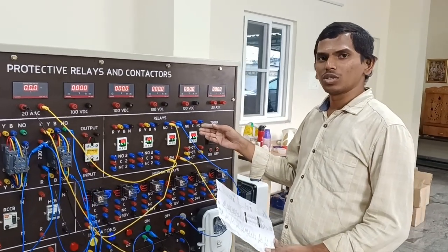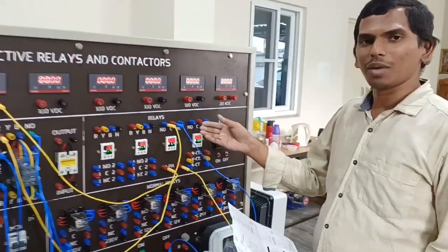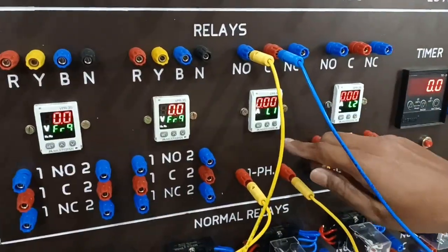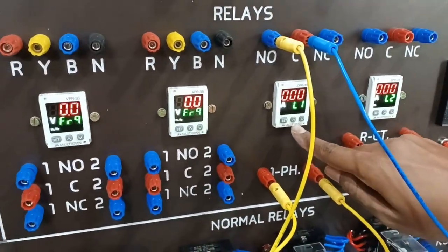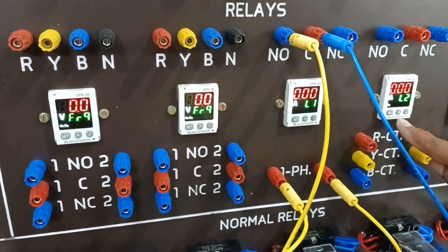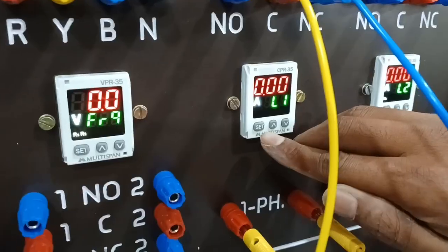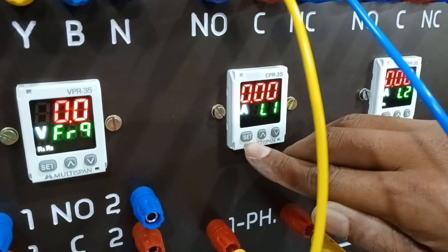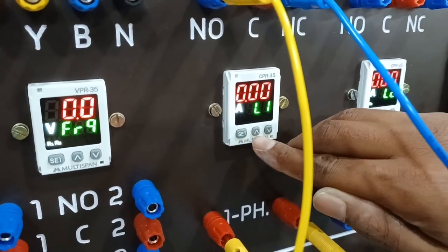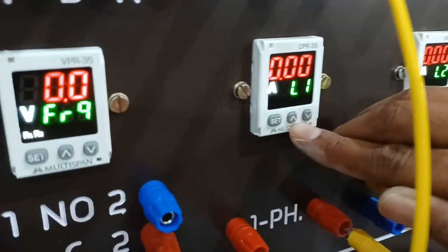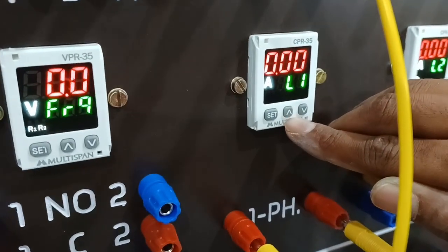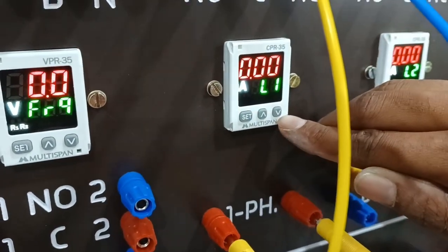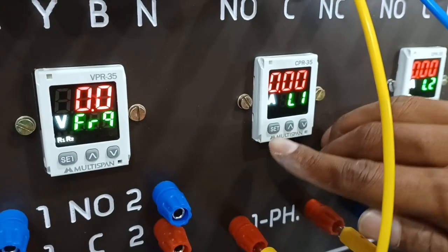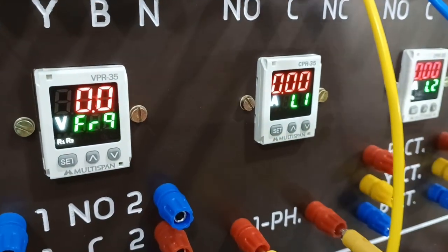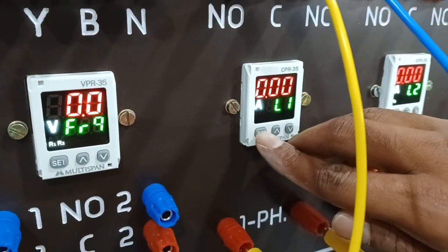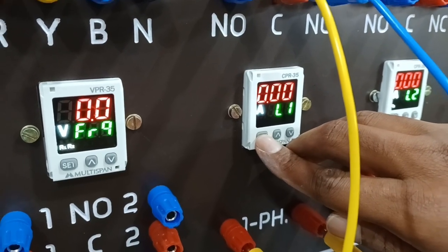Now we can go through the relay programming parameters. This is single phase over current relay, and this is 3-phase over current relay. Coming to relay keys, functional keys, this is set key, this is increment key for increasing purpose, and this is decrement key for decreasing purpose, parameter setting purpose. And for programming the relay, you need to press this set key for 5 seconds.